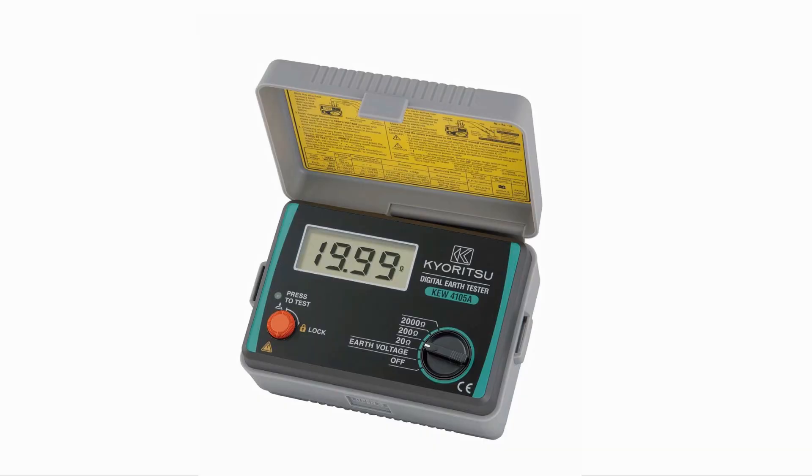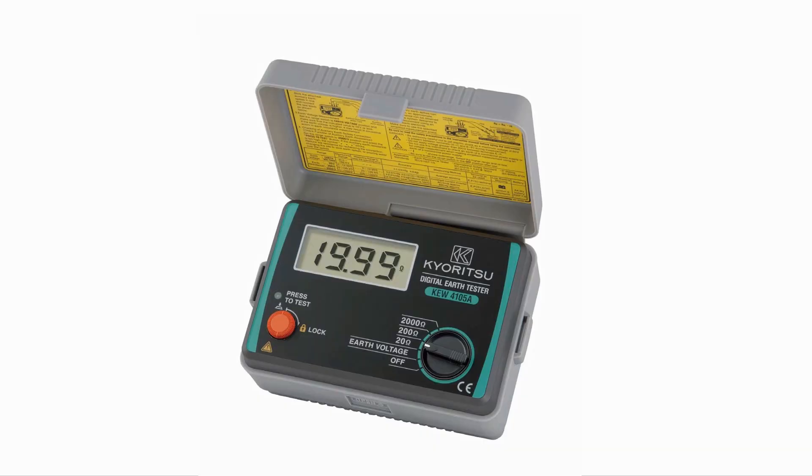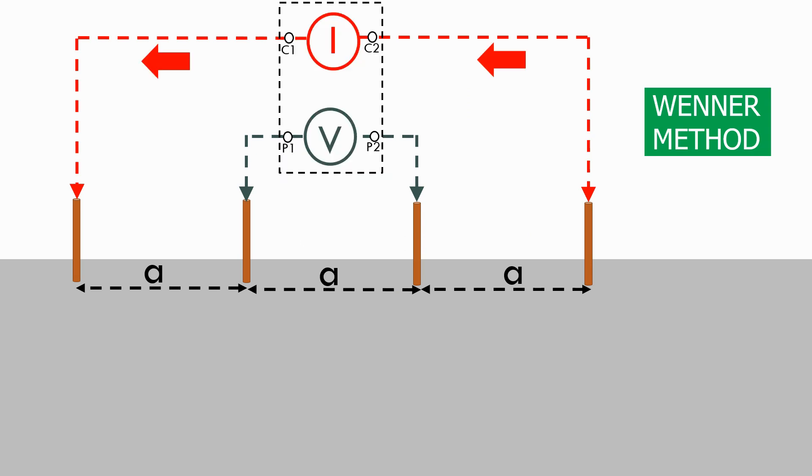Here's a typical example. If we look inside the meter we can see that it injects current into the two outer rods and then measures the voltage on the two inner rods and then uses both the voltage and current values to work out the resistance measured.